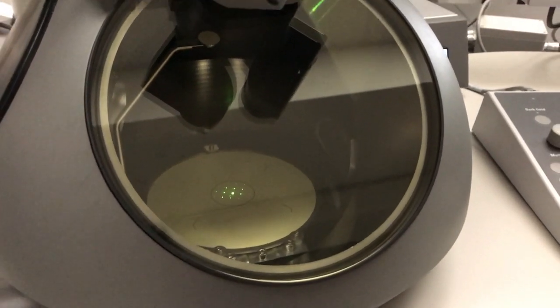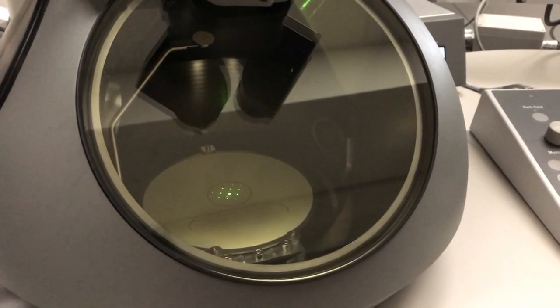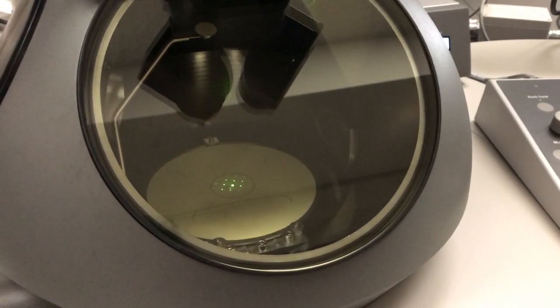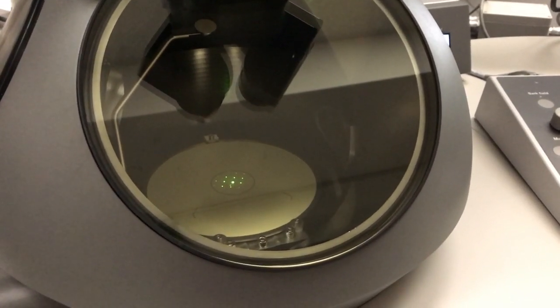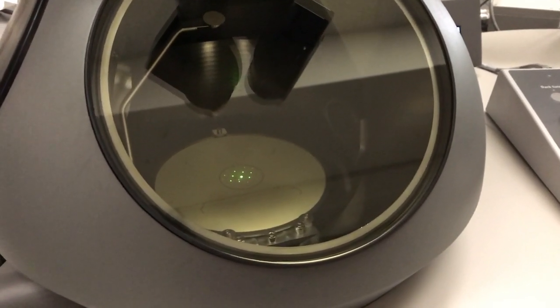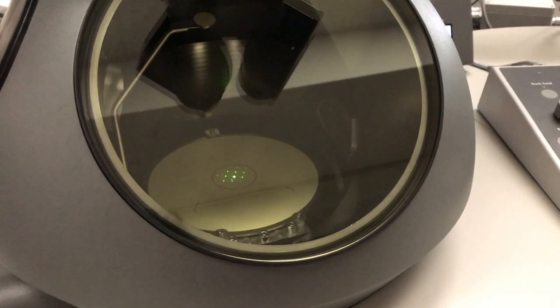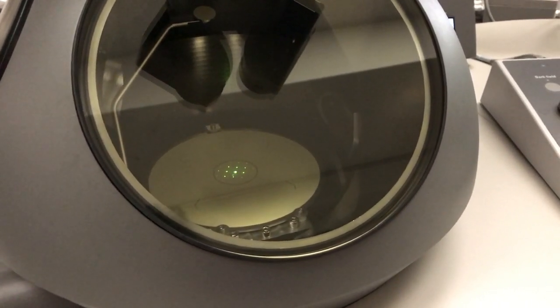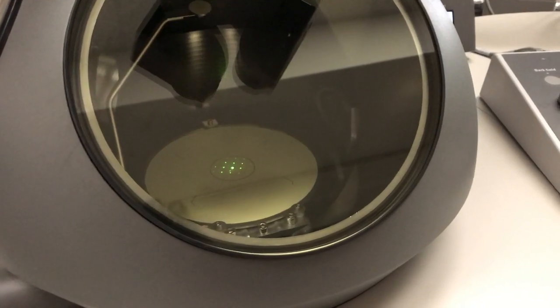You'll also notice that the spots got a lot fainter. What that usually means is that you're not on the same area of the sample, and you're probably on an area that was a little bit thinner than when you started. So when you're adjusting the tilt axes like this, it's not uncommon for your area of interest to move from under the beam from where it was initially.